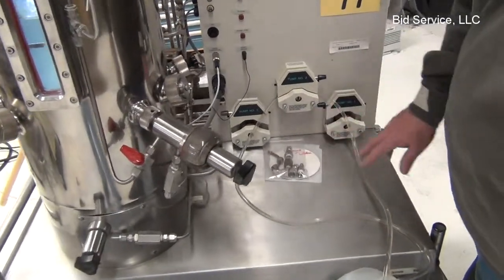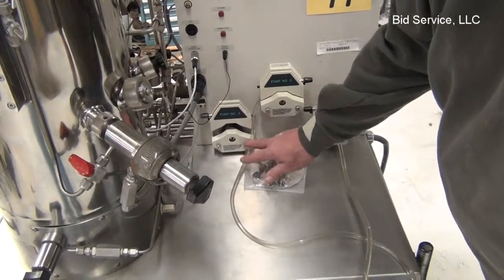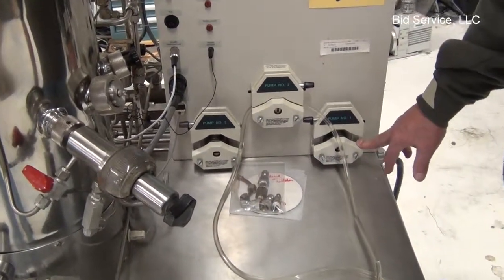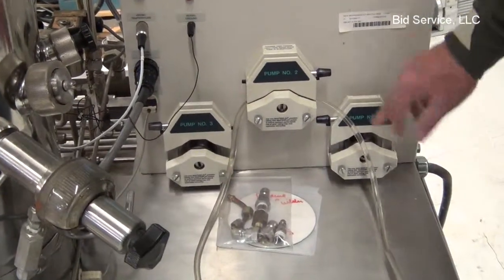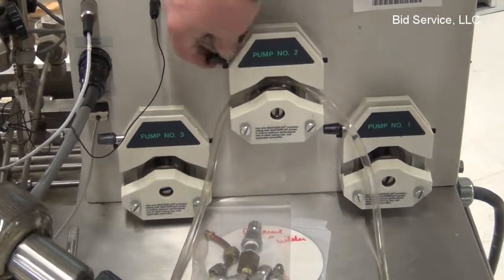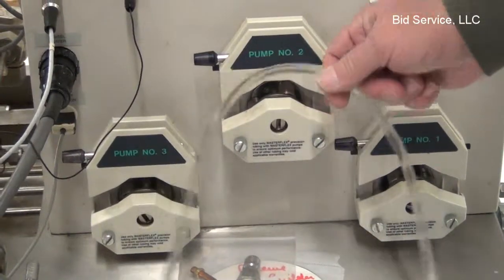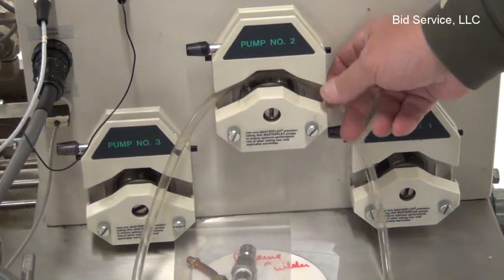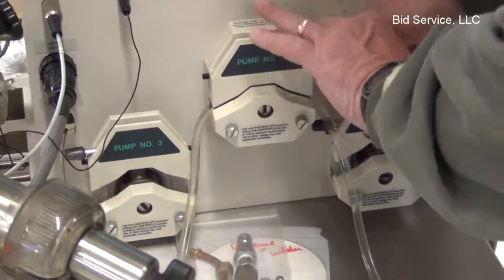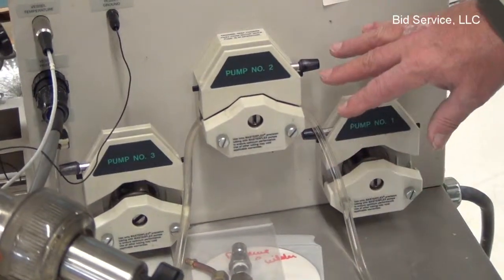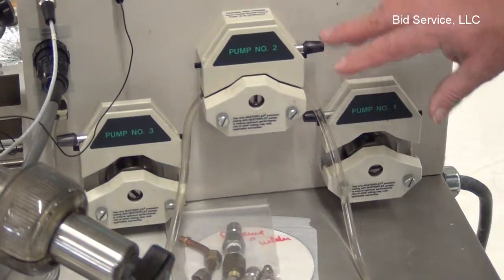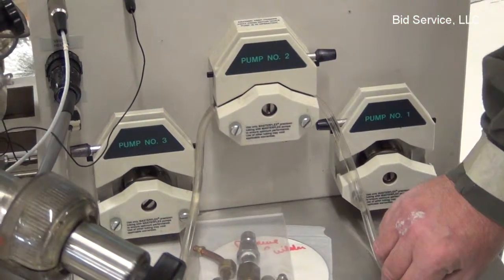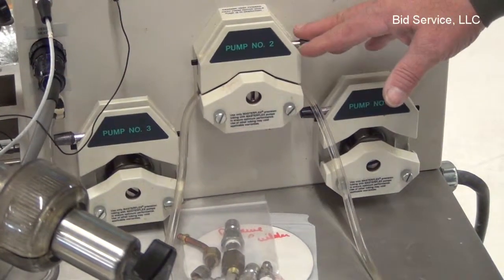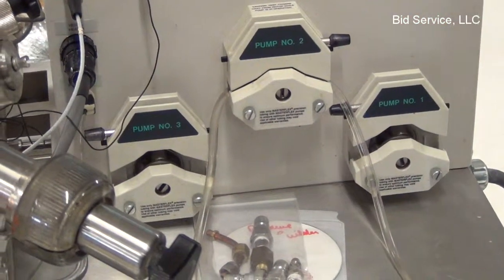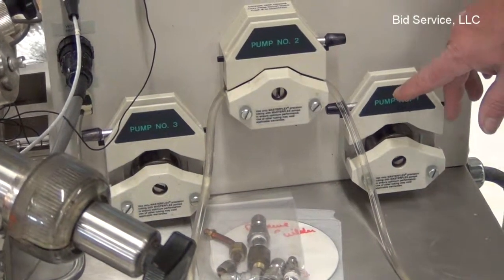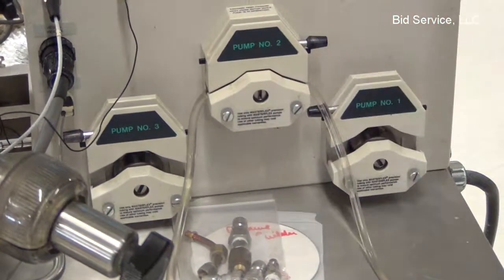Okay, and at the bottom here you have your peristaltic pumps. As you can see, I've got these pumps running just to show that they do in fact run. And pump 2 is off right at the moment. Usually you just have your tubing. I've got an air bubble in the tubing. Put your tubing in, clamp down. The delivery volume of these pumps is controlled by the size of the tubing and how long the pump runs for, which is programmable in your software. It is not speed driven. These do not change speed.